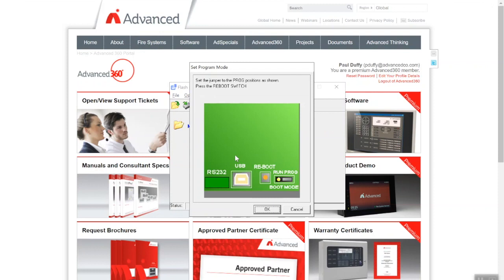So I'm going to select yes, and it's telling you what you need to do: set the jumper to the program position as shown and then press the reboot switch. So once we move this jumper switch across we've got about a 10 second window before we can then click ok. So I just need to follow this process. We're going to move the jumper switch from the run position into the program position and notice the heartbeat LED will go off.